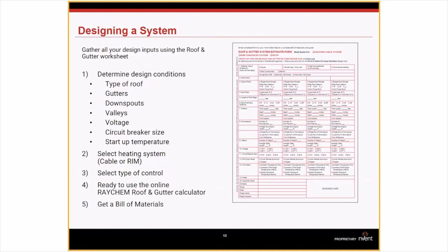Raychem has a roof and gutter form available at www.nventthermal.com to help gather all necessary information from your customer. This includes roof type — shingled or metal — distance between metal seams, overhang size, whether gutters need tracing and their width, depth, and length, downspout height and width to determine single or double trace, and valley locations. You'll also need to know what voltages are available — 120V, 208V, 240V, or 277V for larger systems.